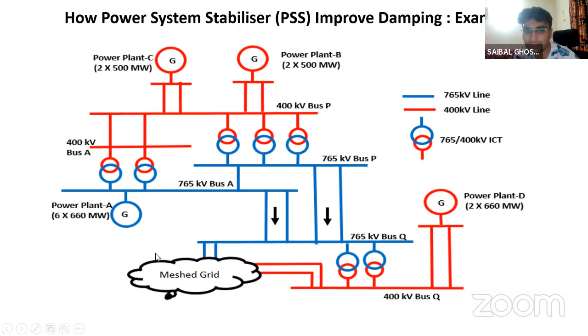Now let us come to some practical examples. This is one case shown here: plant C has two 500 megawatt units connected to the 400 kV and then 765 kV system. Another generator is connected on the 765 kV side. From the 765 kV, outside buses are there, connected to a very strong mesh grid.